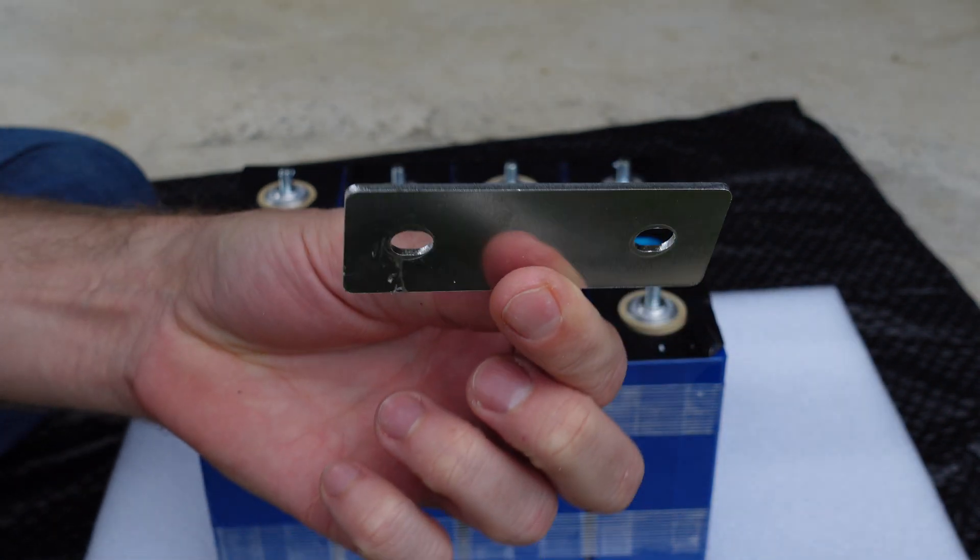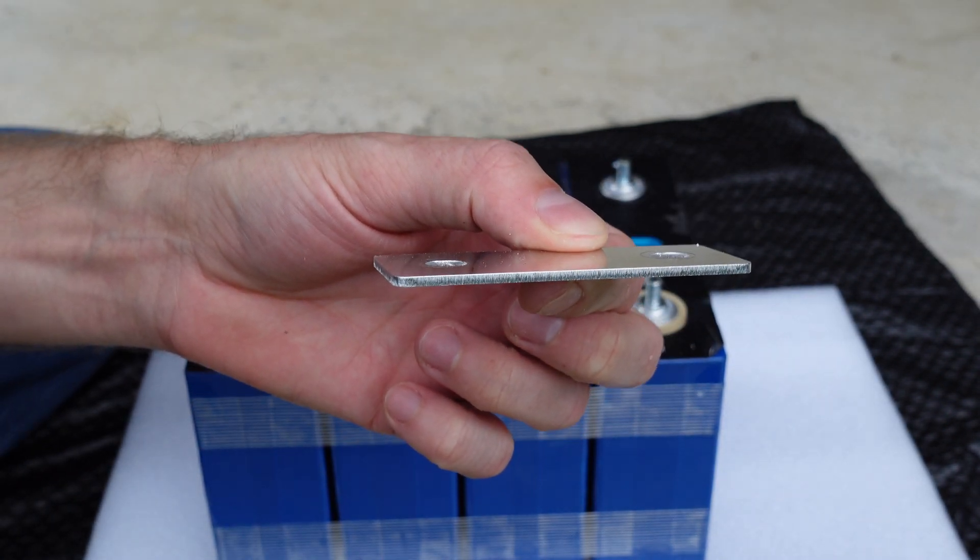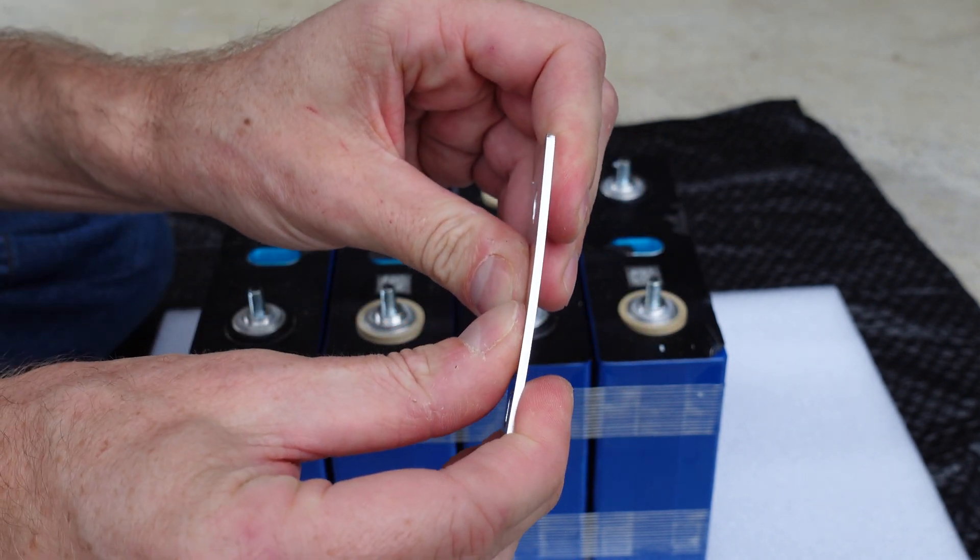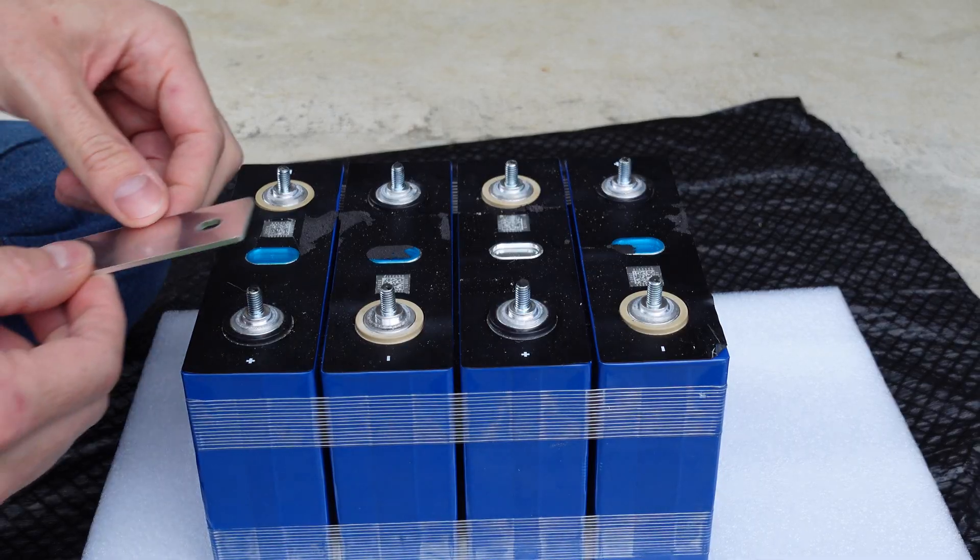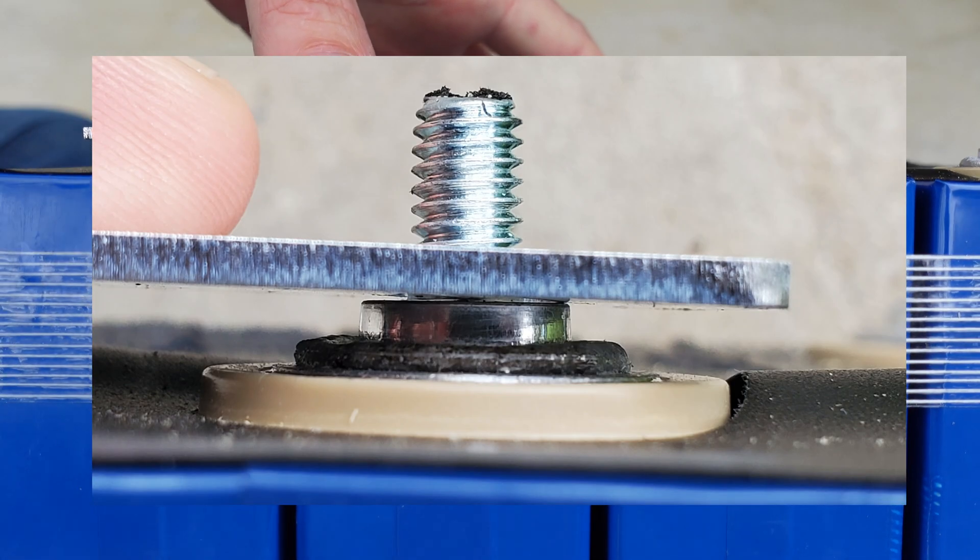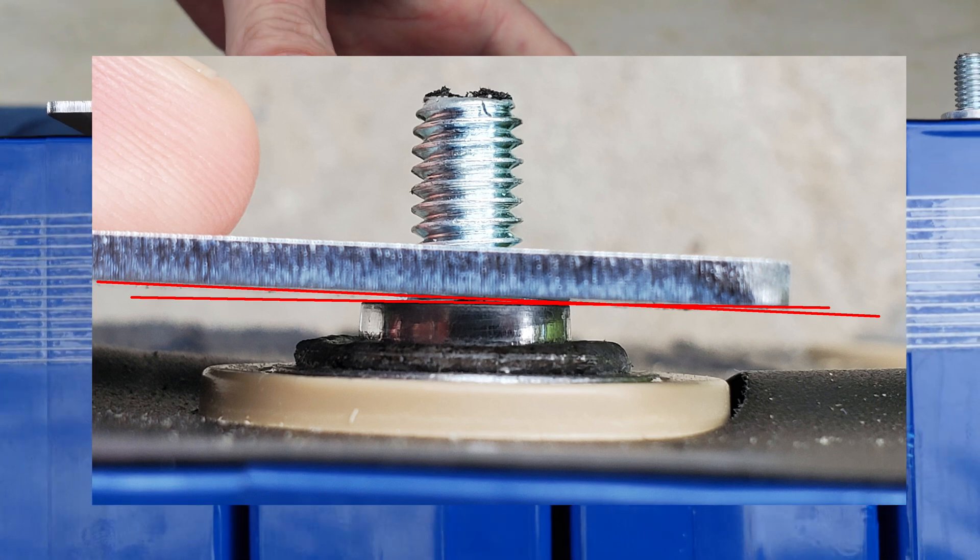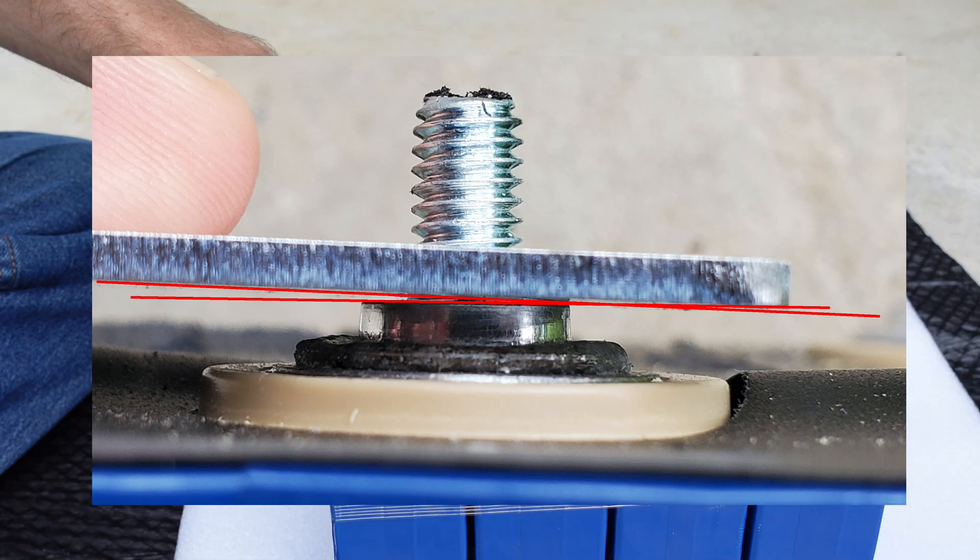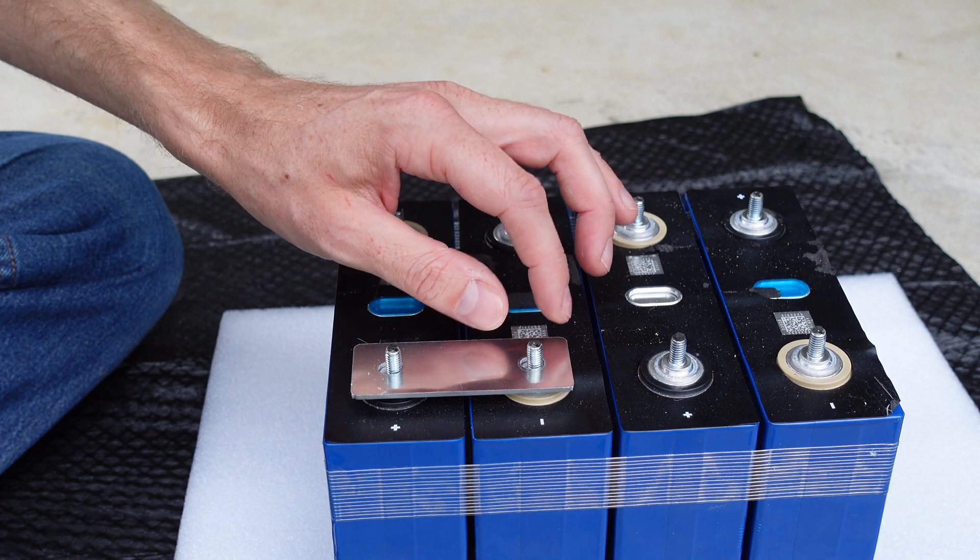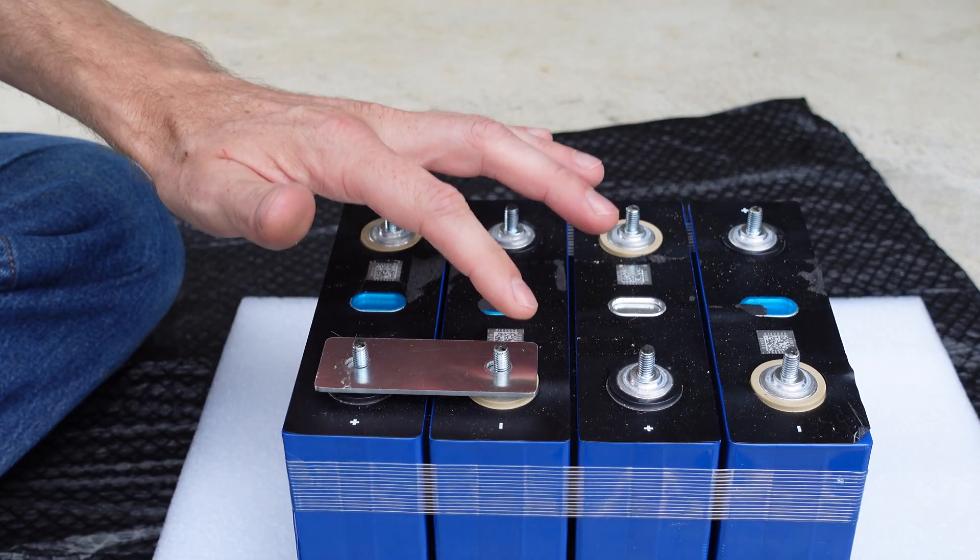This is a solid piece of aluminum. It's rigid meaning it does not bend. There's no hump in the middle and it's not comprised of layers that allow it to bend. So if I set this bus bar across these two terminals on the left side of that white terminal there, it is not sitting flat on that terminal. When you go to tighten down this nut it's going to tighten flat and either the bus bar has to bend or it's most likely going to be this terminal that gives.